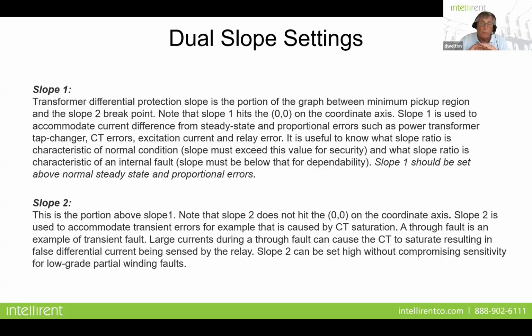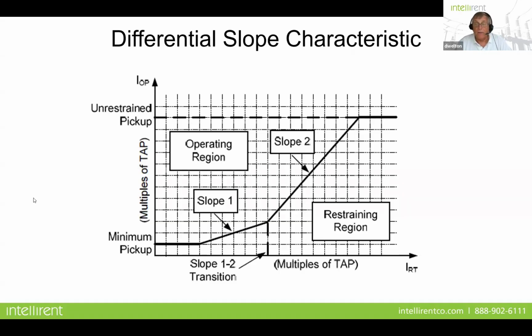And slope 2, you'll notice that slope 1 is at one level, slope 2 is at another, and slope 2 is there to increase the restraint of the differential element. So that if you get a through fault from a transient and it causes the CTs to start to saturate, that will add additional restraint to decrease the sensitivity of the SEL-87 element so it won't misoperate. And it looks like this. So this is your restraining region right here, and this is your first 25% slope, and here's where it goes to the second slope, which is 60%. So this is going to keep your differential relay from nuisance tripping if you have CT saturation or the CTs just aren't that accurate. But once that differential is high enough to indicate that you have a problem internal to the transformer, this is going to be your trip zone up in this region right here.